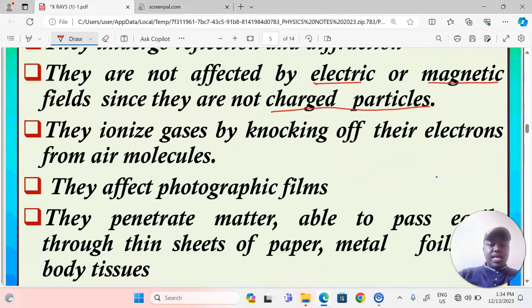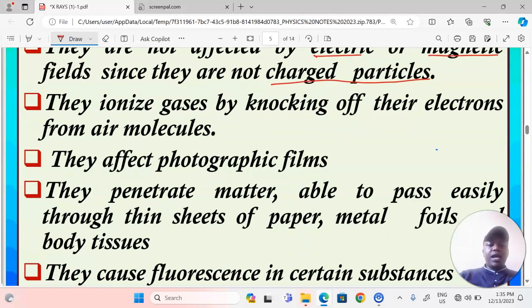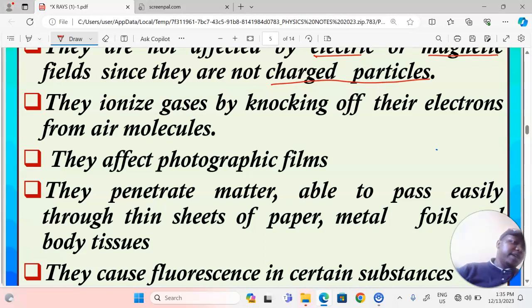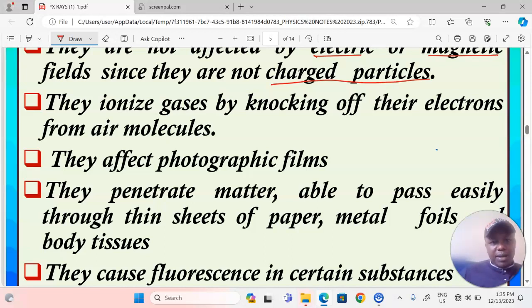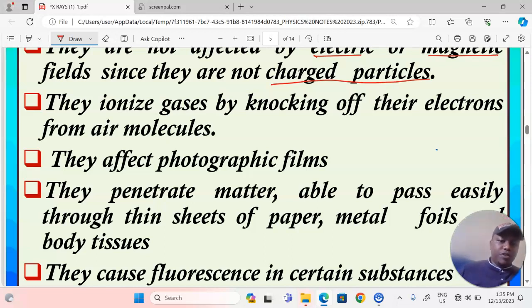X-rays ionize gases by knocking off electrons from air molecules. This is one of the reasons we make sure the x-ray tube is evacuated — to ensure that, due to this property, x-rays don't ionize air particles or gas particles and lose a lot of energy in the process. To avoid the loss of energy through ionization, we make sure that the tube is evacuated.